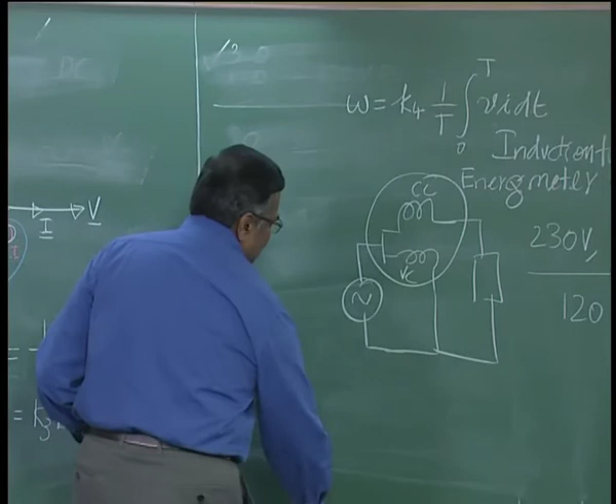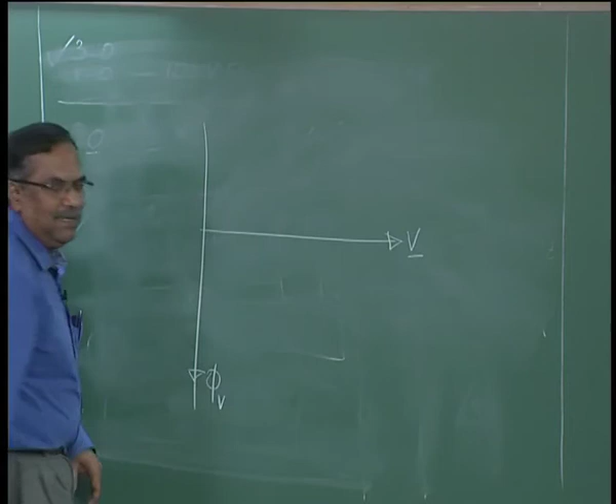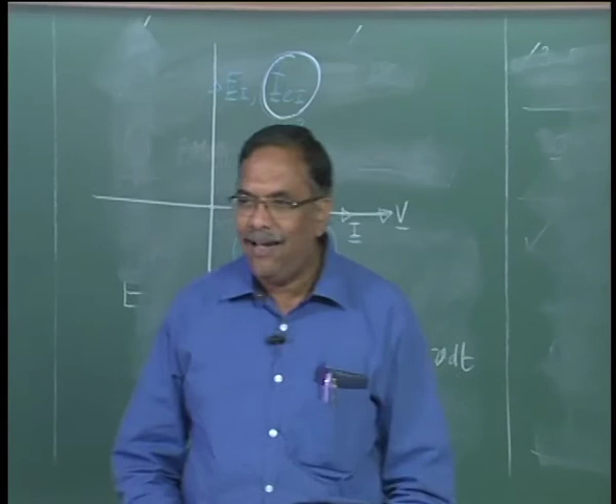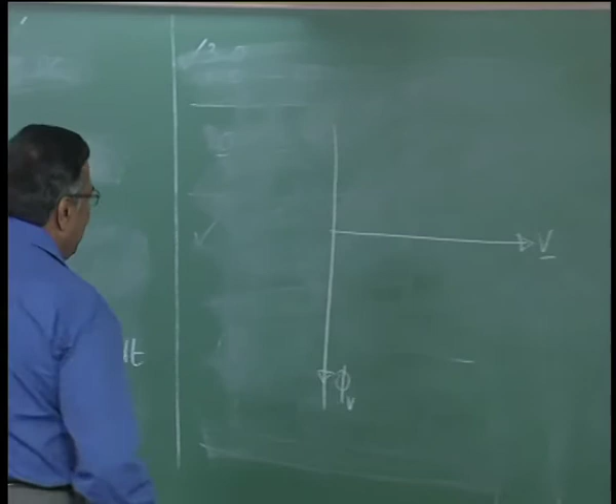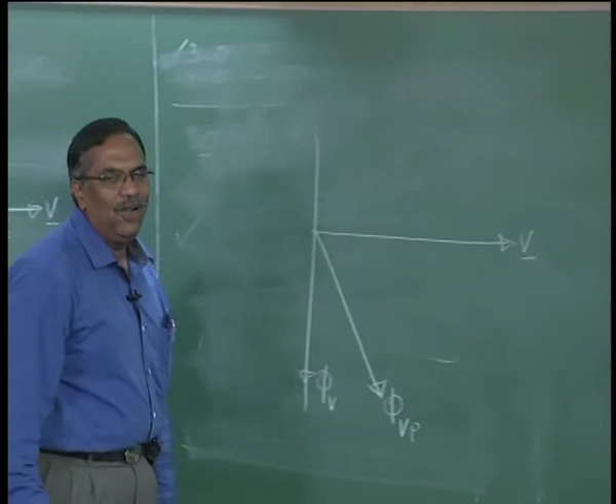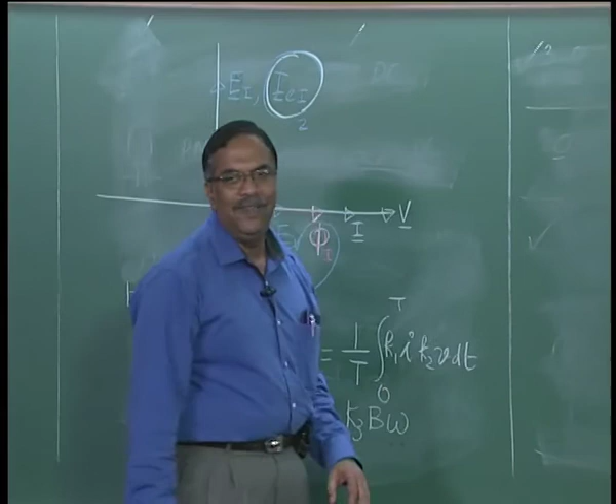Now let us look at the deviations when we make a practical meter. I said this is the voltage phasor and this is the flux produced by it, but in a practical coil this is not exactly true, since that holds only if the coil is a perfect inductor. A practical coil is not a perfect inductor; it has winding resistance. So for a practical voltage coil, I'll call this Vp. Now I know I won't get the nice integral k1 k2 times I times V dt, because the phase is not exactly 90 degrees.